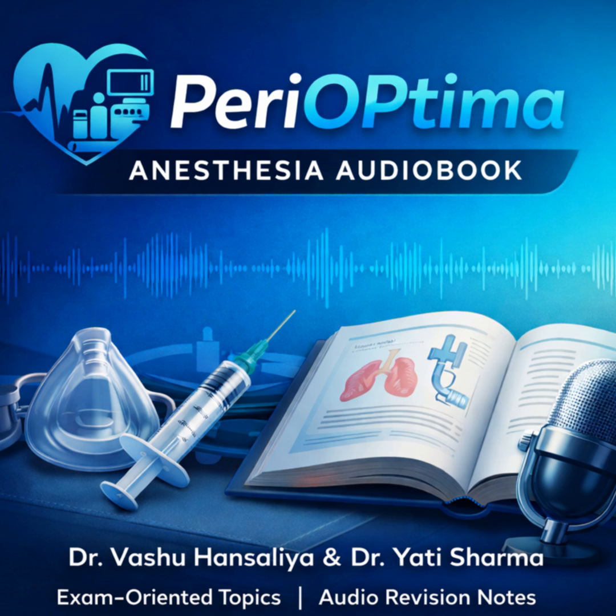The outline mentions bipolar versus monopolar. This seems to be the key to managing the risk. It is your primary defense. You must communicate this to the surgeon. Bipolar cautery is safe. Why is it safe? Because the electrical current travels only a few millimeters between the two tips of the forceps. The circuit is tiny and contained. It doesn't travel through the patient's body.